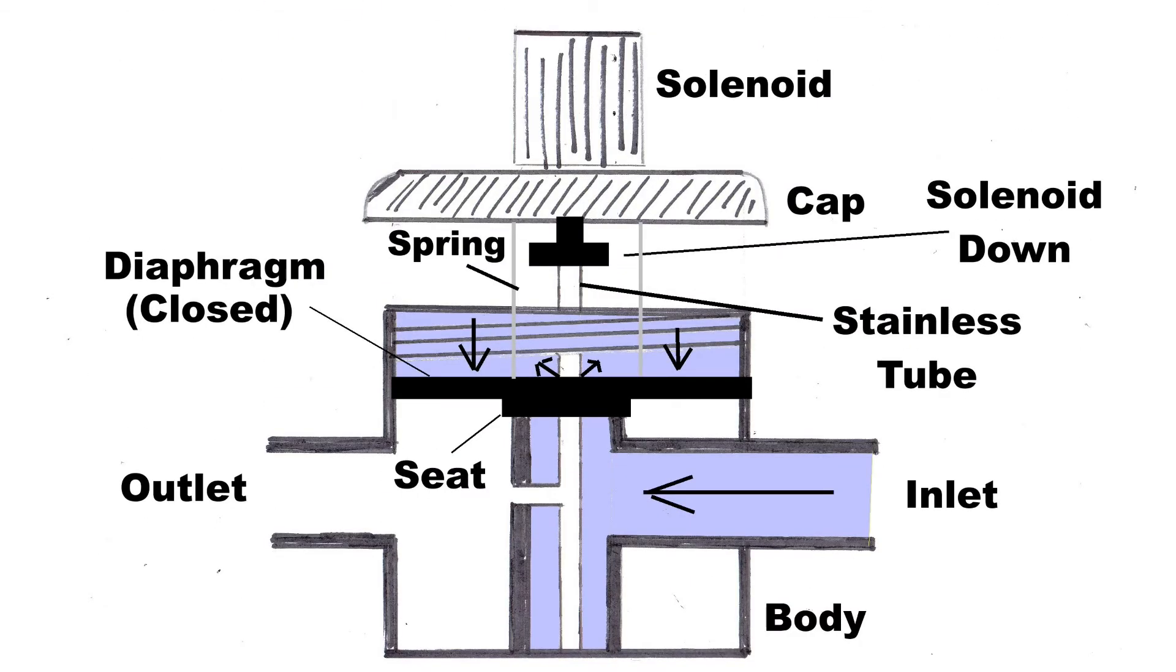Once the solenoid plunger drops back down and blocks the tubing outlet, the pressure between the top and the bottom of the valve equalizes quickly, and the spring helps to force the diaphragm down on the seat.